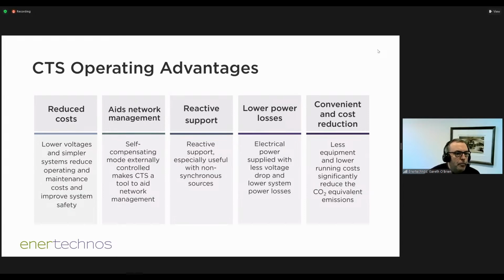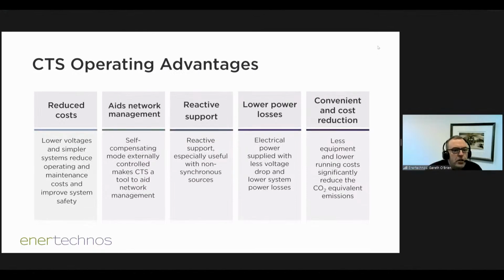Operationally, there are again certain circumstances where you can lower the operating voltage. You might be able to run the whole line at a lower voltage. Self-compensating mode means you can use it to manage the network. It doesn't have to have its supplementary capacitance on all the time. That can be controlled. Reactive support's particularly important with non-synchronous sources. Wind farms, solar farms tend not to produce reactive power. In fact, in many circumstances, they consume it.